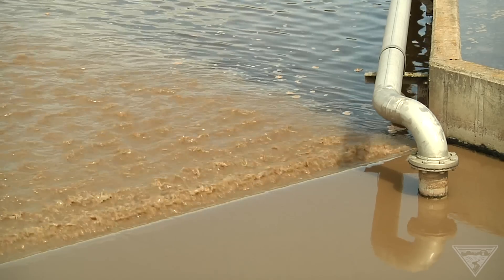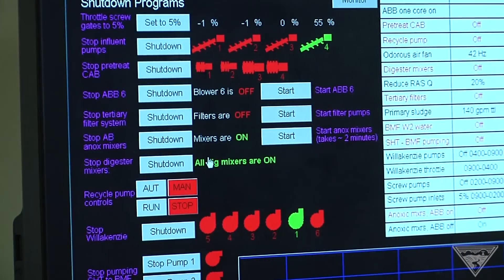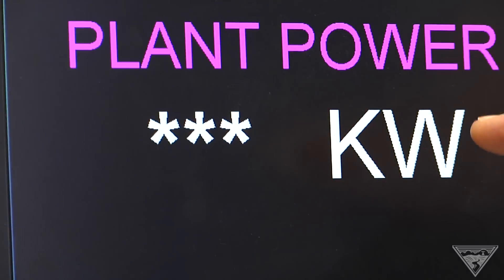This isn't a speedboat — it's more like that big oil freighter going across the ocean. You turn off all the power and it's still going to keep going forward for quite some time before it comes to a stop. When you start adjusting airflows and dissolved oxygen levels, you do it incrementally and slowly, and you watch for the outcome before you move to the next level down. Results revealed that the plant's processes could be interrupted or delayed for an hour, and sometimes up to four, without negative impacts.